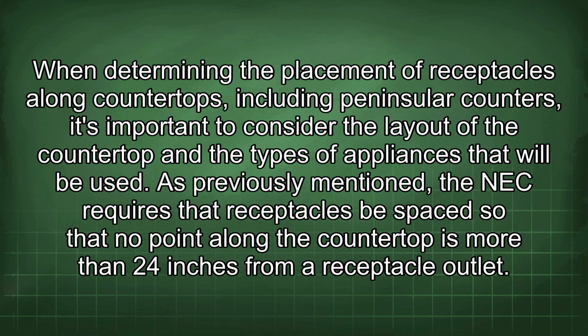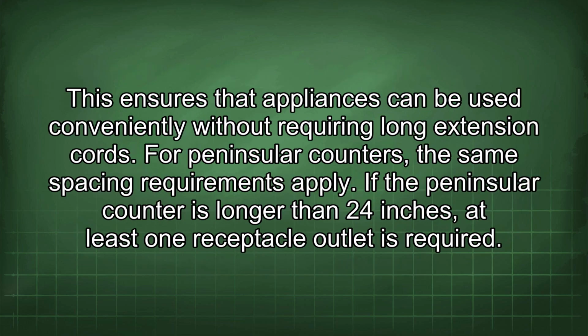When determining the placement of receptacles along countertops, including Peninsular counters, it's important to consider the layout of the countertop and the types of appliances that will be used. As previously mentioned, the NEC requires that receptacles be spaced so that no point along the countertop is more than 24 inches from a receptacle outlet. This ensures that appliances can be used conveniently without requiring long extension cords.